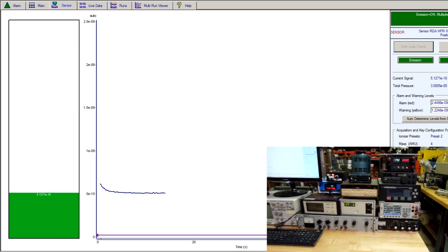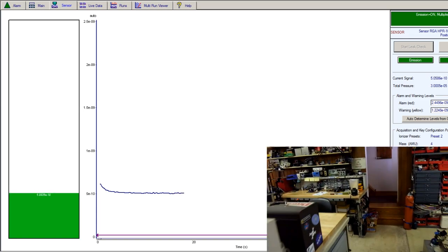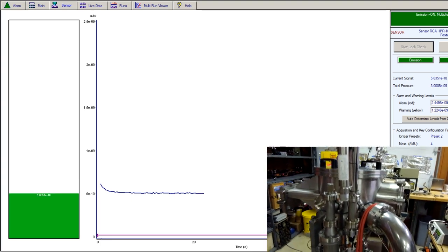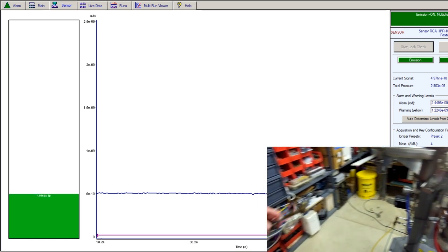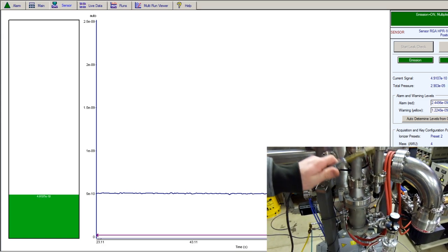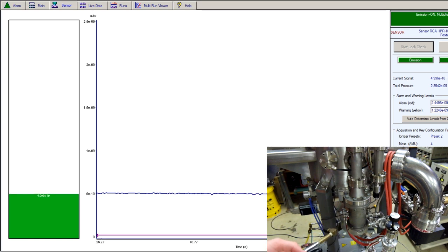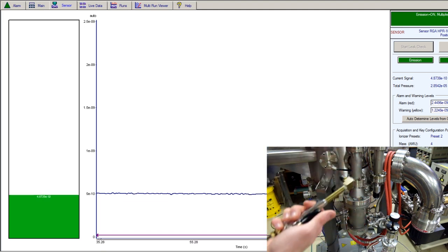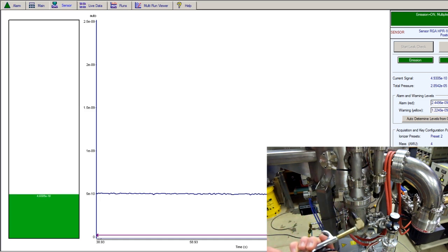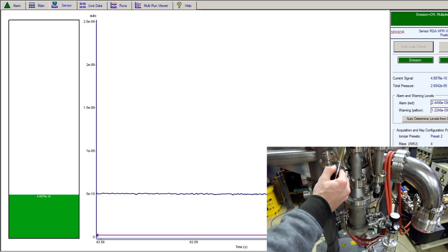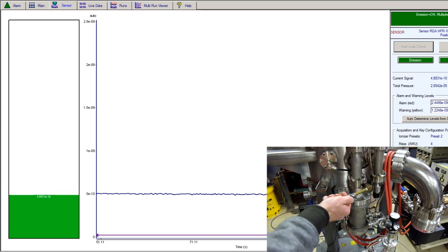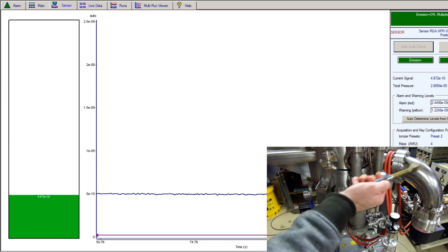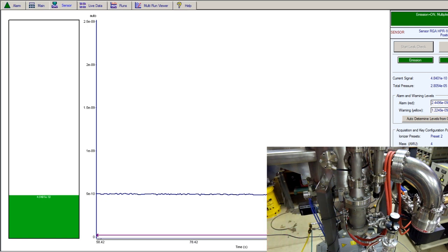I've got helium here hooked to this wand with the flow rate set very, very low. When you do leak checking, you'll start high and work your way low — the reasoning is that helium is lighter than air and rises, so if you start down here and get a high helium reading, it could be that fitting or any of the fittings directly above it. I'll demonstrate what it should look like: slowly pass the helium over any suspicious fittings. These ConFlats have a very low probability of leaking because they're a metal-to-metal seal, but it's possible — so I'd check thoroughly throughout the entire chamber.